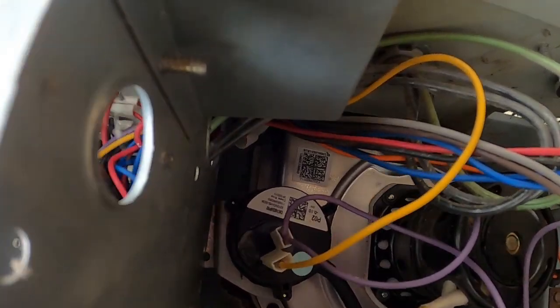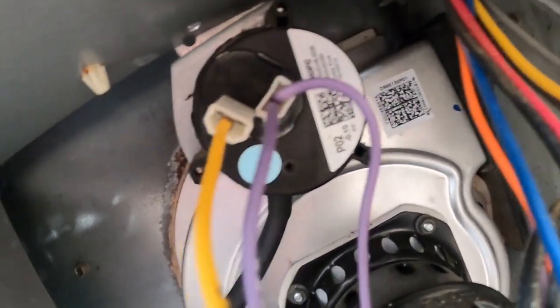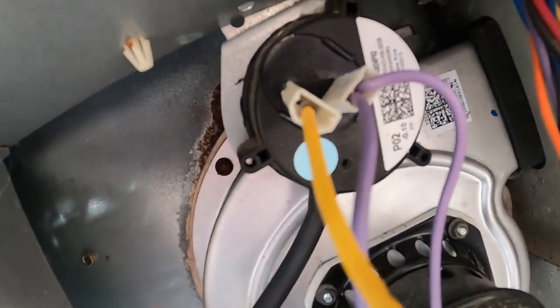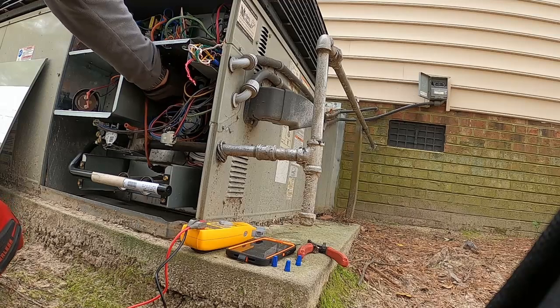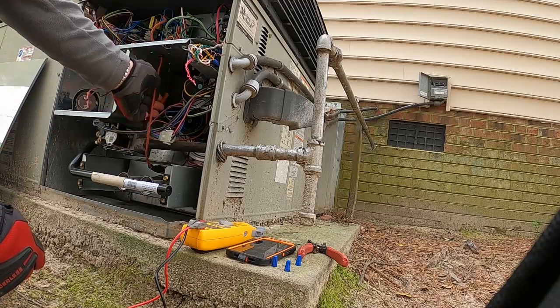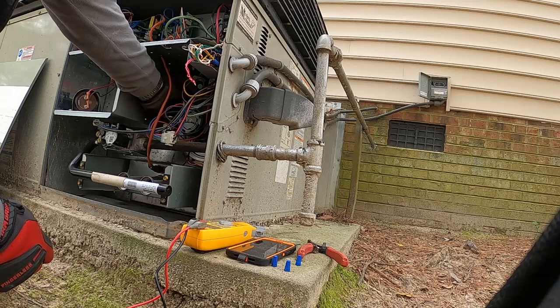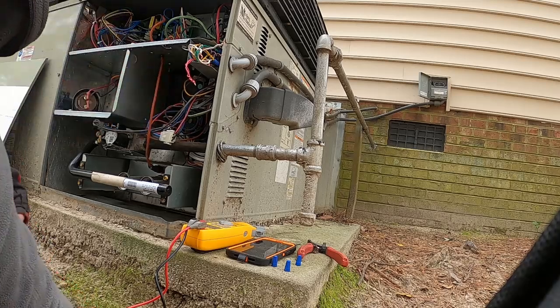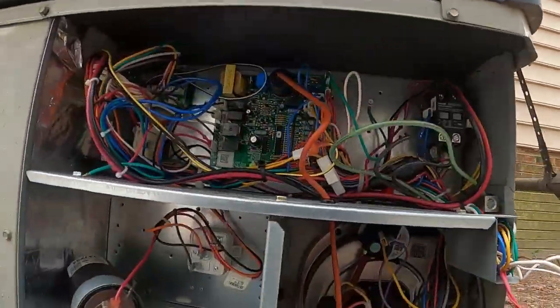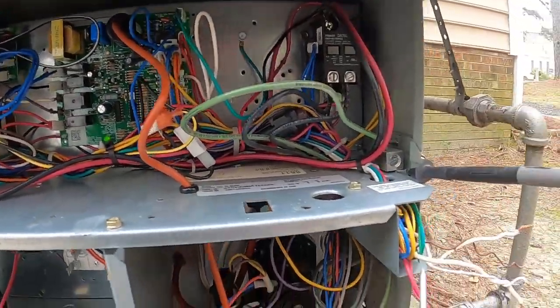Let's see what this switch is rated for. No, that switch is a 0.1. If you look at it real close, it's rated for 0.1, so that should be closed. So now I'm going to check across these two wires. If that switch is closed, I should be getting 24 volts across both of those wires. So I'm going to hook the hose back to the pressure switch. I heard it close, but we're going to double check it with voltage. So put one lead up there on my ground. If it's closed, I'll get 24 volts at both of these wires.